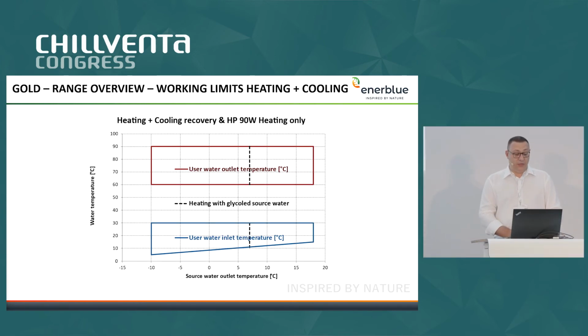For the version with the additional cold water recovery, these are the working limits. So on the lower part, we have source water outlet temperature. So from the cold water recovery, we can have a leaving water temperature from more or less 18 down to minus 10, while in any case, we can have 90-degree leaving water temperature. So for this unit, we have very, very large working limits possible.